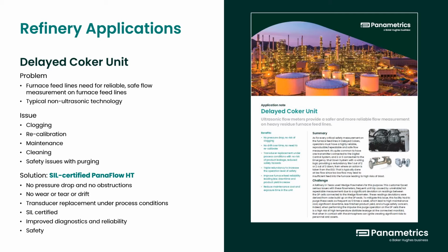The Panaflow HT ultrasonic flow meter does not cause a pressure drop or any flow obstruction since the buffers do not insert into the process. Therefore, the flow is not obstructed and continues down the line like the rest of the piping. The meter does not wear or tear or drift. The Panaflow HT is purely sending the ultrasonic signal back and forth through the process fluid, and the sensing element does not have any associated drift.